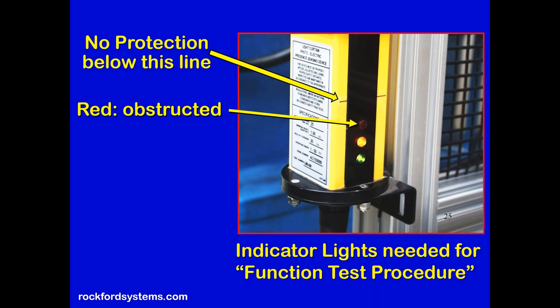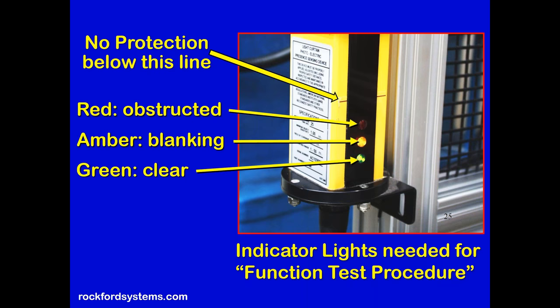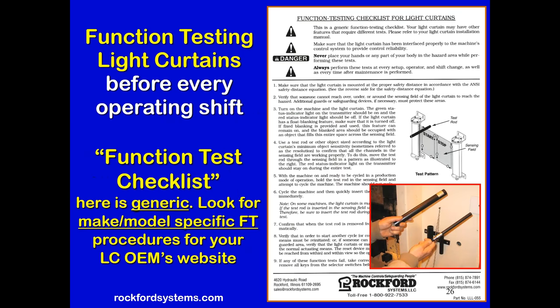Indicator lights on light curtains: you've got red, you've got amber, and you've got green to tell you what the status is. Those indicator lights are needed to do a function test procedure of the light curtain, something you should do before every shift. And here's an example of a function test checklist for light curtains, although, as you can see in the first line, this is generic. Is that what you should be using on a light curtain for function testing? Well, ideally, no. If your light curtain manufacturer is still around, you go online and get the make and model specific function test procedure that they suggest for that light curtain. So don't settle for generic.